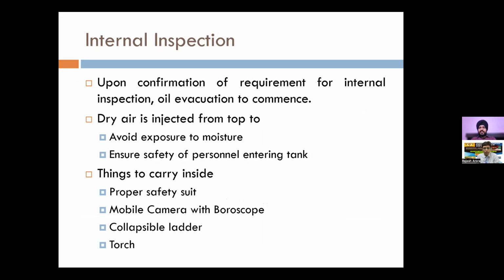So oil evacuation needs to be done, mostly in a 500 MVA transformer. There is around 100 kL of oil, and you need to have a proper setup. An oil evacuation and filtration plant needs to be there, then tanks, and simultaneously as you are evacuating the oil, the dry air needs to be injected from the top. This dry air ensures that there is no exposure of the winding to moisture, and the personnel who are going to enter the tank for the internal inspection are also safe because they are able to breathe properly.